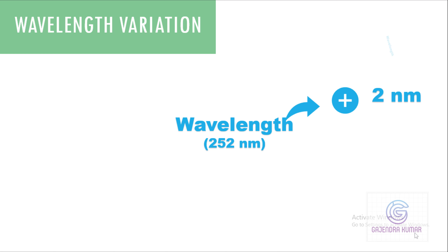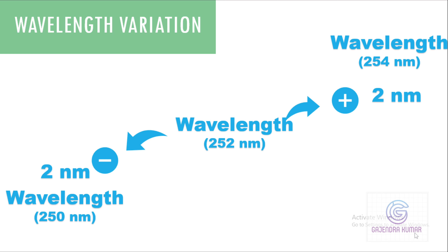This is our wavelength, that is 252. Again, you need to select the upper range and lower range. In this case, it is 2 nanometers. That means a wavelength of 254 in the higher range, and 2 nanometer lower range means 250 nanometer in the lower range. So we have three different wavelengths. So in the experiment part, we need to perform the experiments in all three wavelengths.